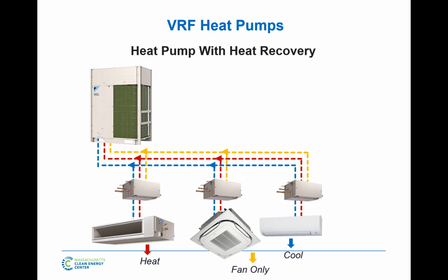It's liquid, suction, and hot gas. So if this unit here wants cooling, this changeover box knows that, and it'll say, okay, here's the cold supply for you, and I'll take back return. Whereas over here, this changeover box sees that its fan coil wants heating, so it'll do the opposite. It'll switch over the other way and say, here's the hot supply. That's how this one can cool while this one can heat.